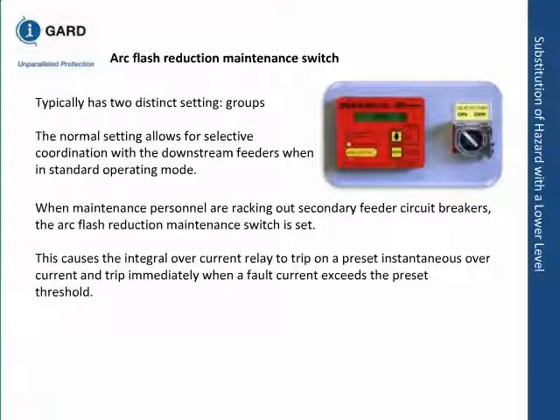So what a maintenance switch does is, when somebody is working on it, you click the switch and the upstream device is set at instantaneous. So it'll clear faster. Of course, it requires some human action, so it cannot be considered an absolute that it'll work automatically. Now you also have to go back and reset them. This is one of the options allowed in the National Electrical Code 2011 under 240.87. One of the options is allowed.